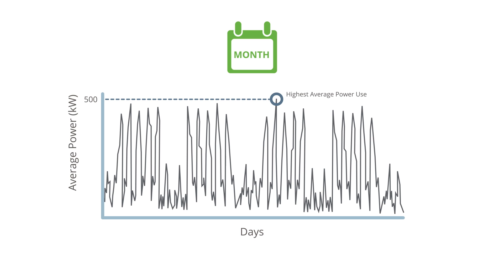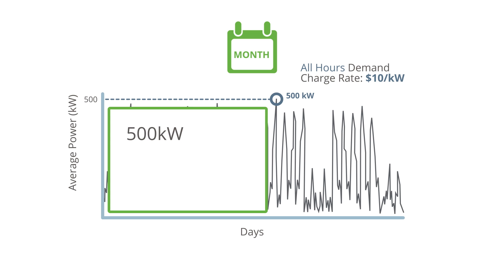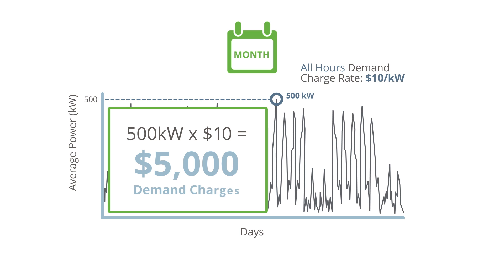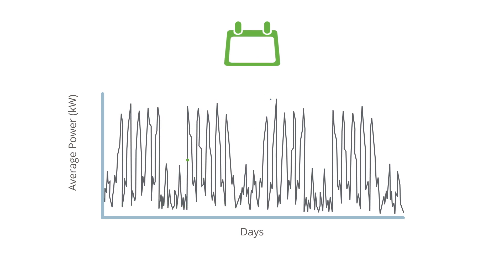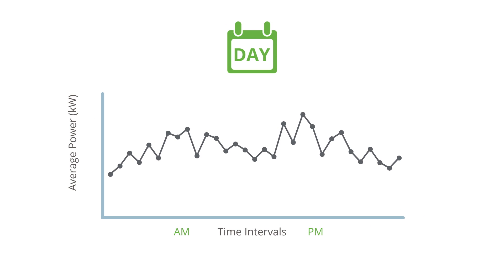It's calculated by multiplying that highest amount by an all-hours demand charge rate. If the highest average power usage within a billing cycle is 500 kilowatts and the all-hours demand charge rate is $10 per kilowatt, the customer would be billed $5,000 for all-hours demand charges that month. On top of all-hours demand charges, there are often additional charges assessed for the highest average power usage within certain times of the day. Peak demand charges, for example, are calculated by multiplying the highest average peak period power usage in a billing cycle by the peak demand charge rate.